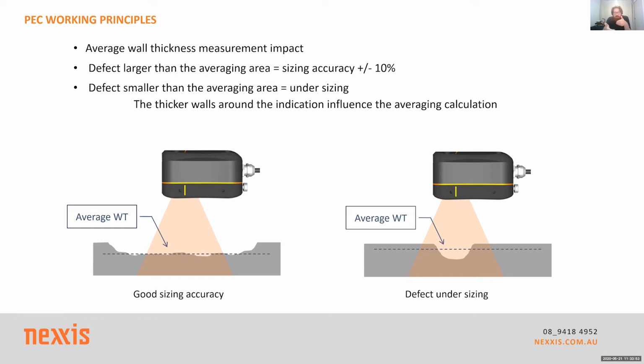That's when you're in that thicker wall thickness. So we were at 19 millimeters wall thickness for this job, and it can handle a higher range of lift off. And then there's also a large probe, which is probably about 250 mils long, quite a big probe. That's for your really thick or really high lift off situations. It's hard to say this probe's for this situation because it's all a relationship. If you have a thicker wall but little lift off, you might get away with a smaller probe. If you have a thick wall with lots of lift off, you'll need the bigger probe. If you have a thin wall with lots of lift off, you might need the medium probe.